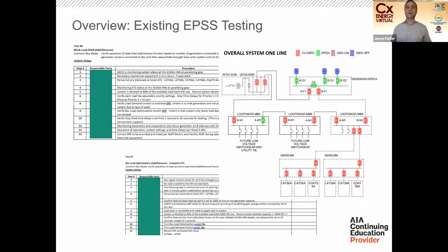It's not emergency power system versus normal power. We're talking about demonstrating a system, and that may involve a dual utility fed system with a main auto throwover sequence, or a normal power loop distribution. How do we simulate a failure of utility while demonstrating the emergency power system, minimizing impact and helping the client understand what is being impacted?